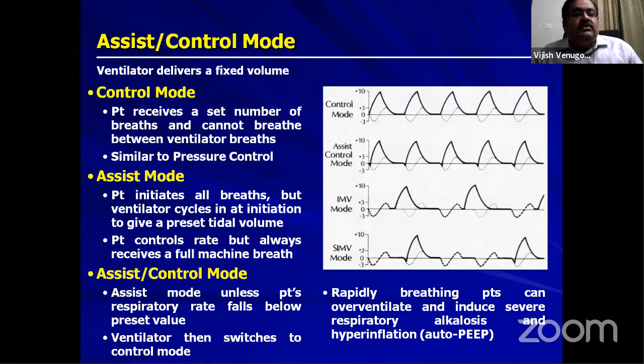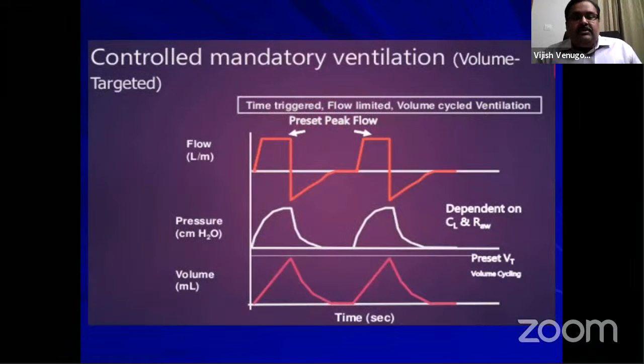Now coming to the assist mode, here the patient initiates all breaths, but the ventilator cycles in at initiation to give a preset tidal volume. So the patient controls the rate, but always receives a full machine breath. So here you can see this is a controlled mandatory volume targeted breath, and there is a square wave pattern.